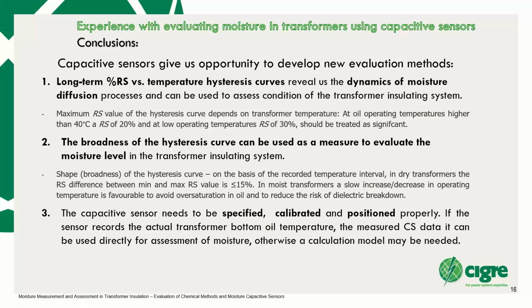So these are several conclusions which concern capacitive sensors. Capacitive sensors give us the opportunity to develop new evaluation methods. As we saw already, they show us the dynamics of moisture between solid insulation and liquid insulation. And it is very important to have the transformer temperature, which is simultaneously also recorded by the capacitive sensors. And the evaluation criteria are about 20% relative saturation for capacitive probes, tank top, and 30% tank bottom. The broadness of the hysteresis curve is also an indication which can be used to evaluate whether a transformer is wet or not.